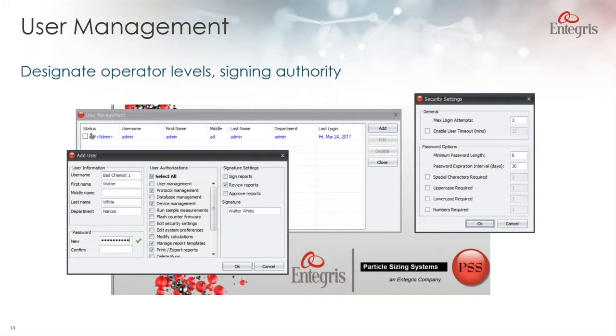When we first install the systems, one of the first things we do is sort out the user management, because we want people who use the system to have their own password. Then we might also want different users to have different levels of authorization. So we'll set up a new user, give them a name, decide what they are authorized to do. Can they run the instrument? Can they sign and approve results? Can they change protocols, etc.? Are they allowed to sign reports, is what is set up here. And then we can also organize the basic security settings. So these are important functions that we'll sort out before we start having the operator using the system.